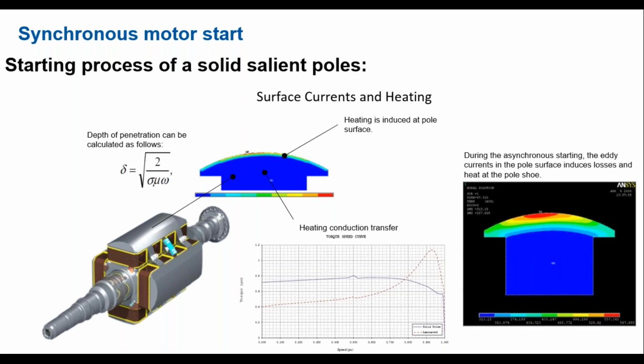We're just having a look at the heat buildup during one start of these machines. And this is due to high eddy currents that are induced and concentrated at the surface of the pole shoes. The graph compares, you can see the red dotted line is the typical starting torque curve of a laminated salient pole design, and the blue curve is the starting torque curve of the solid integrated pole design. And you can see a much higher starting torque is available from this machine.